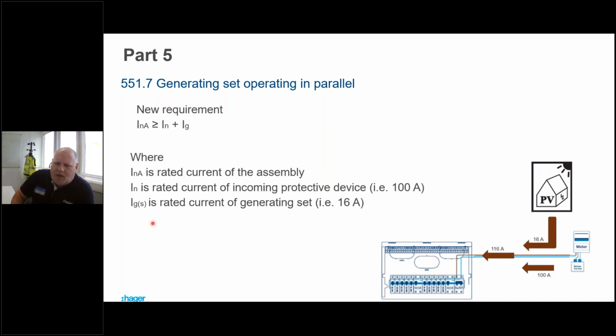Now, this is the new bit where we've got to factor in IG. IG is the rated current of the generating set. Most PV installations will generate about 16 amps. All of a sudden, we've realized that these boards are being given the option of 116 amps, but most of them are only rated to 100 amps. Okay, that could cause us a problem.